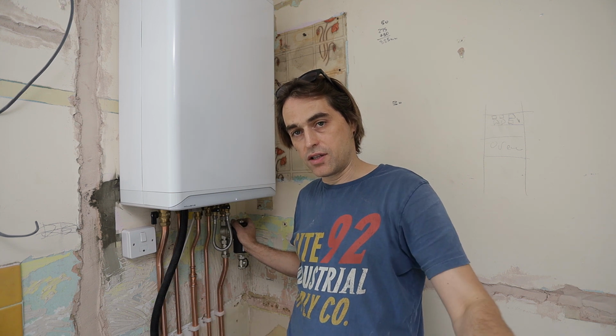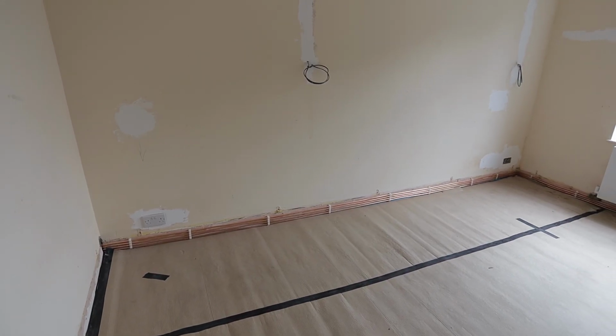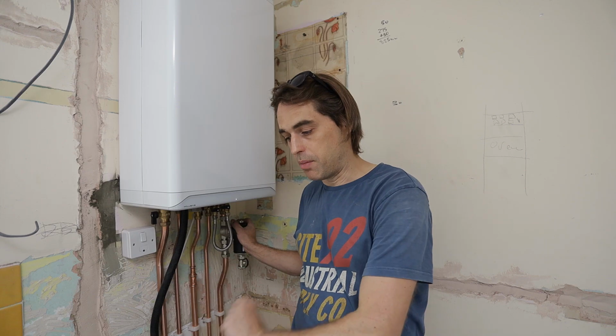And I used microbore because with the heat loss of below 4 kilowatts in this 1-bedroom flat, there's just no need to run any bigger pipes. We are fine with head loss and velocities of water in pipes on 10 mil, no problems whatsoever. Another thing is there are concrete floors everywhere, so the pipes were run in some areas above the floor, and since they are only 10 mil pipework, the carpenter on the job will put a batten on top of them and then 6 mil plywood in front of the pipework, so it will look like a regular 22, maybe 25 mil skirting board, and will hide the pipework quite nicely.